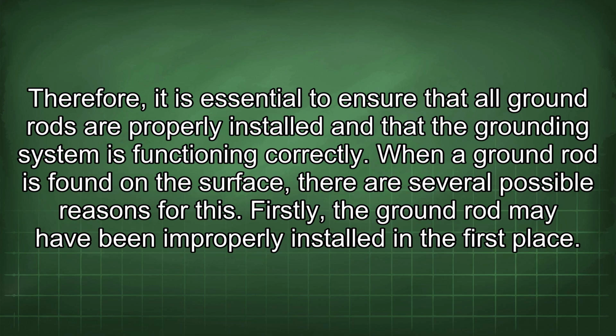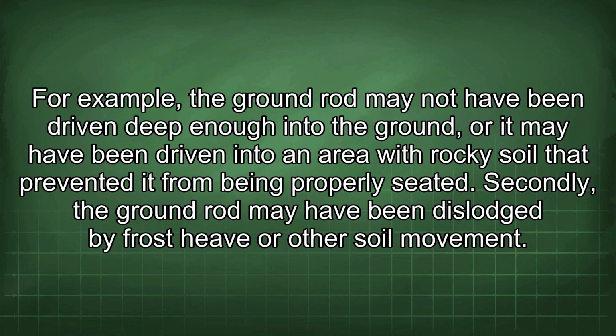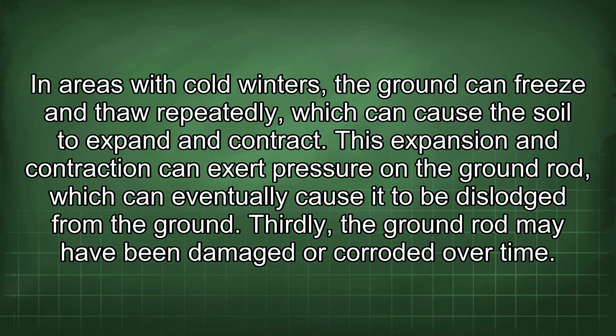When a ground rod is found on the surface, there are several possible reasons for this. Firstly, the ground rod may have been improperly installed in the first place. For example, the ground rod may not have been driven deep enough into the ground, or it may have been driven into an area with rocky soil that prevented it from being properly seated. Secondly, the ground rod may have been dislodged by frost heave or other soil movement. In areas with cold winters, the ground can freeze and thaw repeatedly, which can cause the soil to expand and contract. This expansion and contraction can exert pressure on the ground rod, which can eventually cause it to be dislodged from the ground.